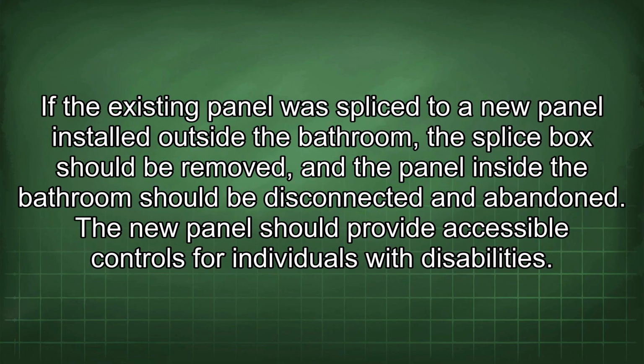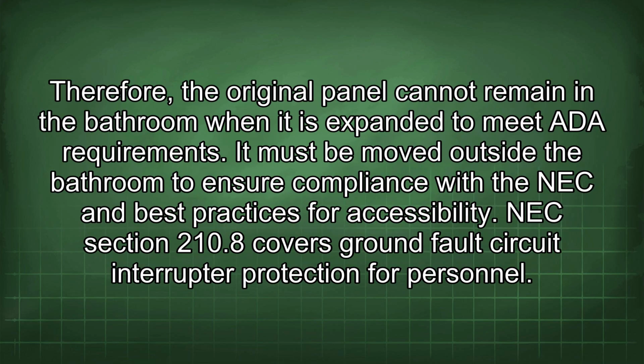If the existing panel was spliced to a new panel installed outside the bathroom, the splice box should be removed and the panel inside the bathroom should be disconnected and abandoned. The new panel should provide accessible controls for individuals with disabilities. Therefore, the original panel cannot remain in the bathroom when it is expanded to meet ADA requirements. It must be moved outside the bathroom to ensure compliance with the NEC and best practices for accessibility.